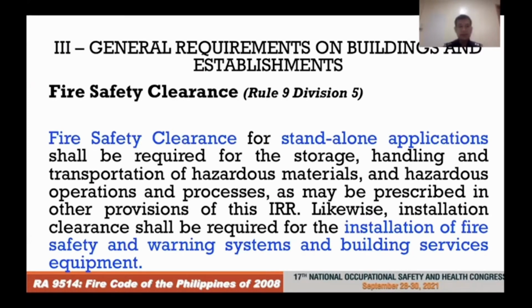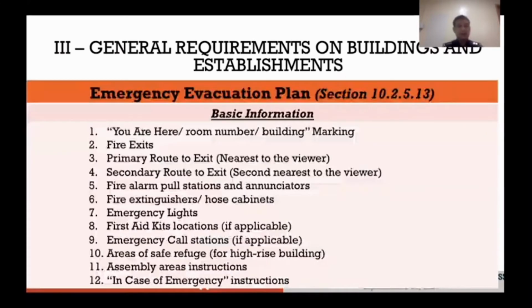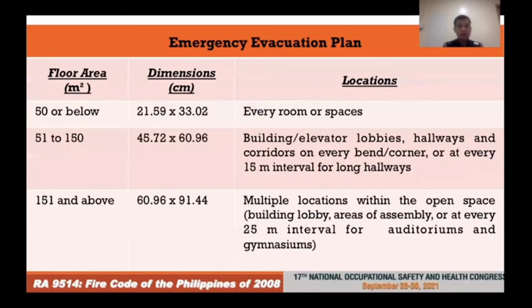The fire code also now requires the mandatory posting of the emergency evacuation plan. In the old implementing rules and regulations, only places of assembly buildings were required to post. Now, under Section 10.2.5.13 of the revised implementing rules and regulations, all buildings are now required to post emergency evacuation plans in conspicuous locations within the premises of the building. And the basic information enumerated therein is the required information that must be present in your emergency evacuation plan. Also, there are dimensions required depending on the floor area of your establishment or your building. So, enumerated in the slides are the dimensions required based on areas.